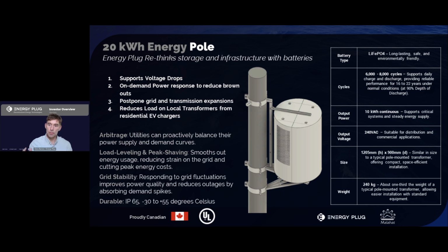These can support then. So once they're plugged in, really the primary application of these is on the secondary side in a residential environment. So when you see these traditional transformers, whether it be a pad-mounted transformer or one on a pole, they take higher voltage and step it down for residential use. Typically, you'll see 10 to 15 homes, sometimes even less, that are fed per transformer. And so this is coupled with those units. What that does then is we connect on the secondary side. So when that collection of homes has an increase in demand or surge, we can then supplement that, so that you see there the load leveling and peak shaving.